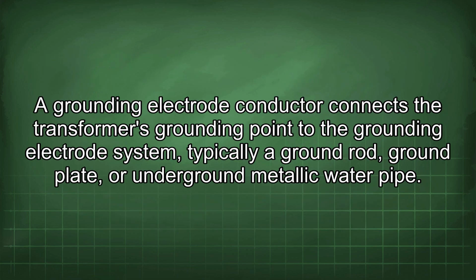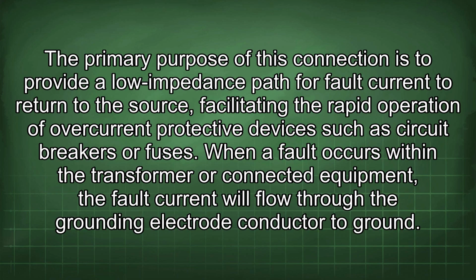A grounding electrode conductor connects the transformer's grounding point to the grounding electrode system, typically a ground rod, ground plate, or underground metallic water pipe. The primary purpose of this connection is to provide a low impedance path for fault current to return to the source, facilitating the rapid operation of overcurrent protective devices such as circuit breakers or fuses.